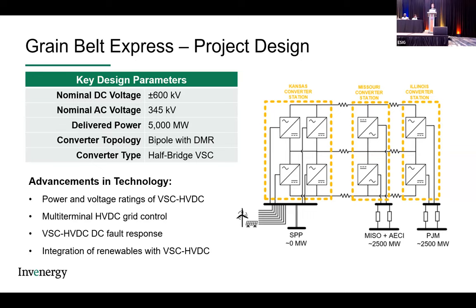And then another piece is a DC side fault response. So when there's a fault in the DC line, the coordination to clear and restart quickly from that fault is a key piece of the project. And that's something that this will be pushing forward as well.